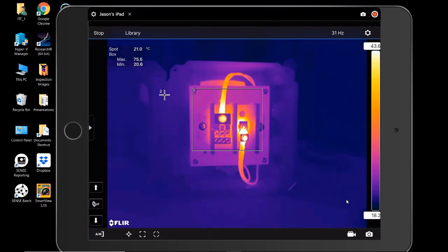Okay, now over towards the right, underneath the scale, there are 2 options for capturing data. The camera, the furthest towards the right, looks like a little digital camera. This captures a single JPEG. The camcorder type icon will capture an MPEG video. Now, these are not radiometric videos, so there's no post-processing with the FLIR software for these. They're just color movies. Just keep that in mind. To do a radiometric, a thermographic recording, you have to use the PC software over USB or over Ethernet, depending on the camera model.